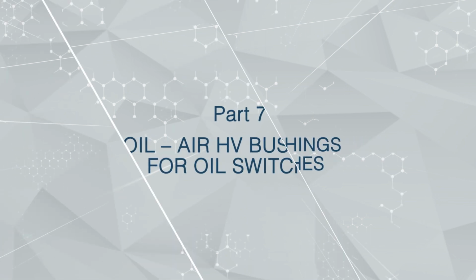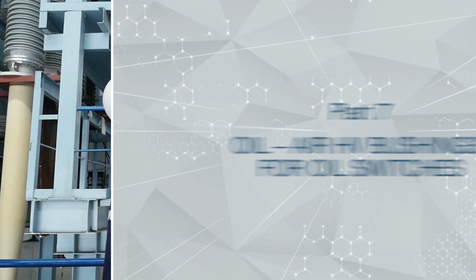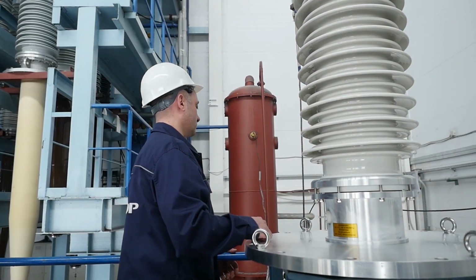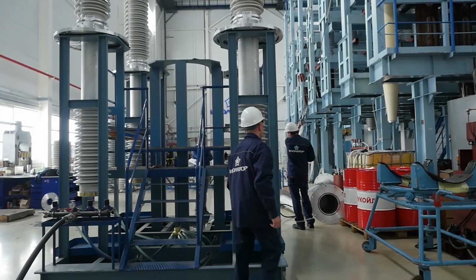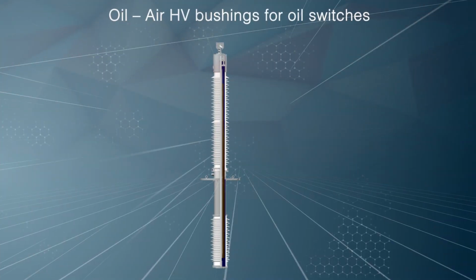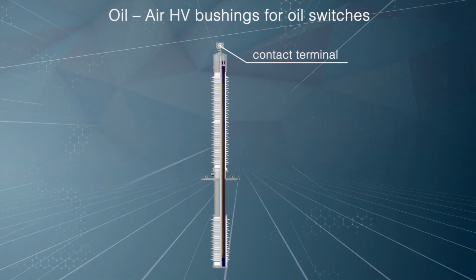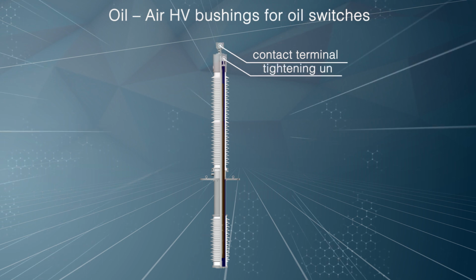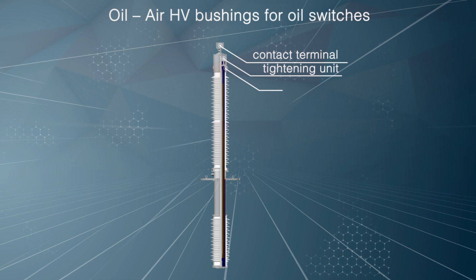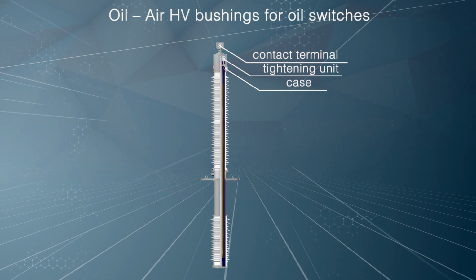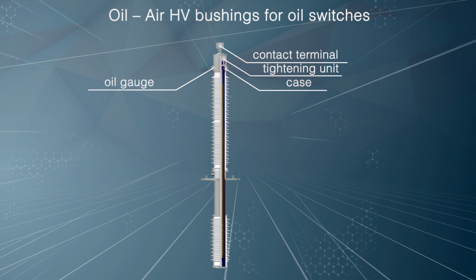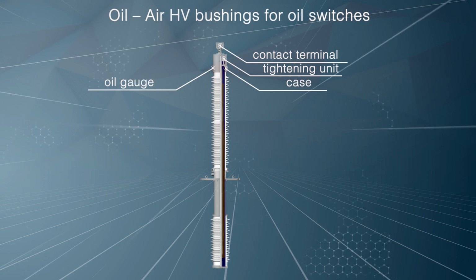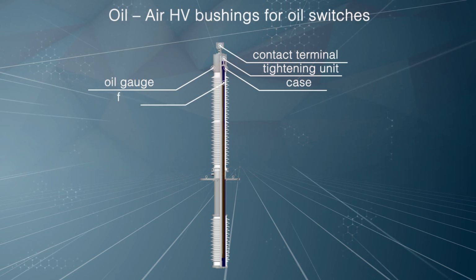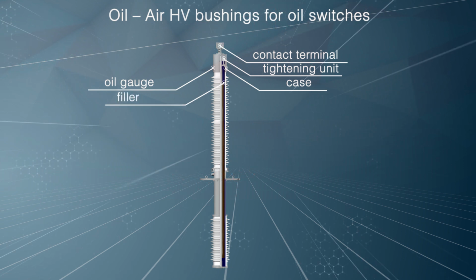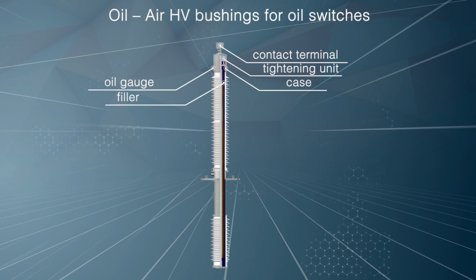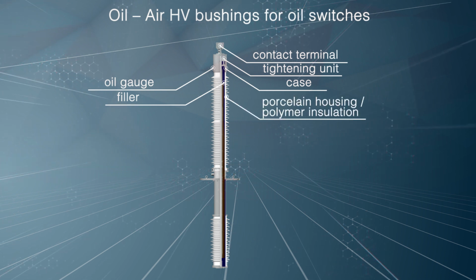Oil-to-air high-voltage bushings for oil switches. Bushings are the main insulating element of the oil circuit breaker, ensuring its reliable and secure operation. The contact terminal is made of brass and is meant for connecting the down conductor terminal of an aerial power line. The case is used for installation of the following components of the bushings: gas cushion, tightening unit, oil gauge, only for 220 kilovolt bushings. The filler, oil, protects the internal hollow of the bushing from moistening. The porcelain housing is an external insulation of the bushing. The insulation core is an internal insulation of the bushing.